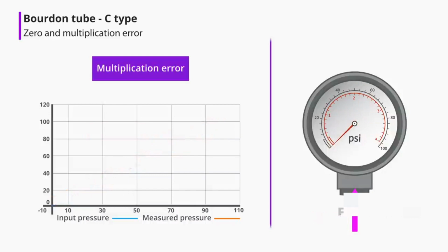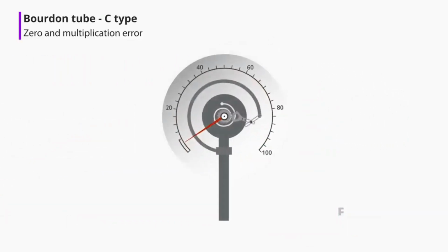Okay. Let's repeat. We'll apply pressure and watch the readings to determine what type of error exists. With 0 psi in, the gauge indicates 10 psi. With 50 psi in, the gauge indicates 50 psi. With 100 psi in, the gauge indicates 90 psi. This pressure gauge has a multiplication error because the total movement of the mechanism does not equal the total change in pressure input.